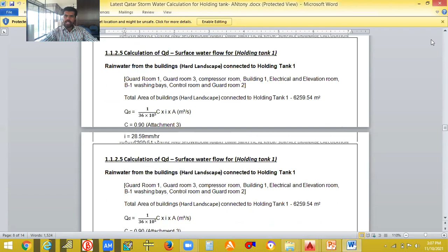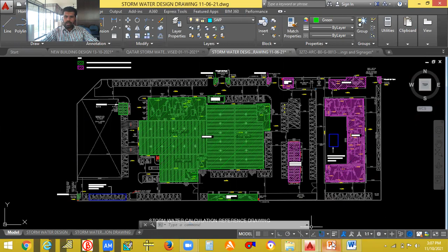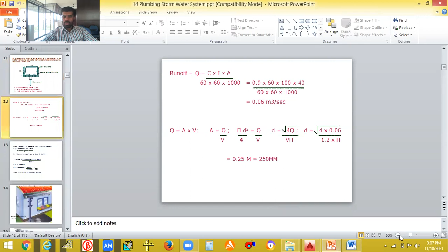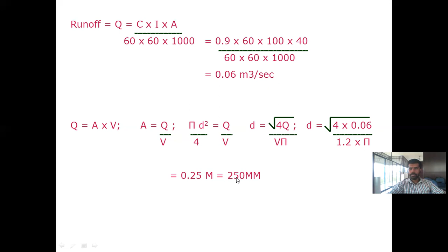So there is nothing more in this. You have to understand only this one. You should be able to know this formula. The C value you will get from that table. The I value is the intensity of rainfall, that also you will get from the table. A you can calculate: length into width is the area. Then find the Q value, and you will get it in cubic meters per second. You can convert this into cubic meters per hour also. Then what you have to do is go to this formula and you can find out the diameter of the pipe.